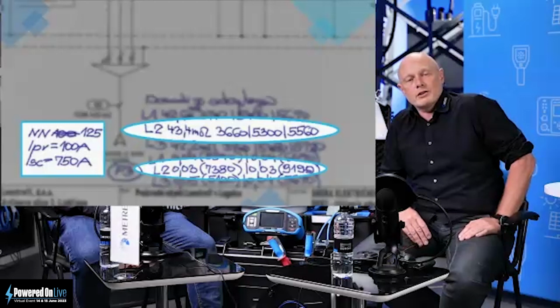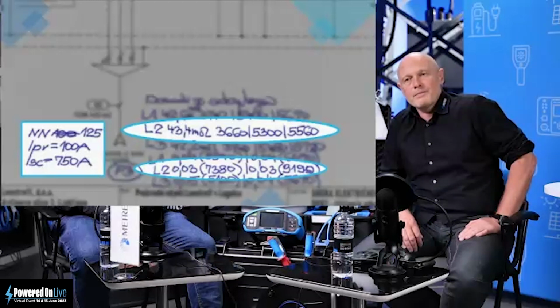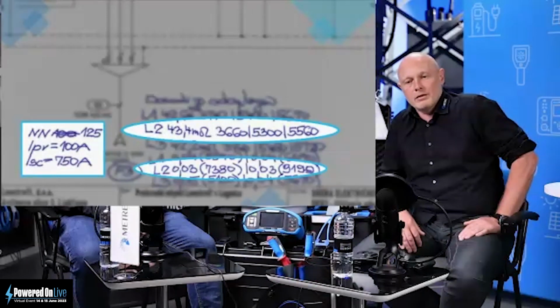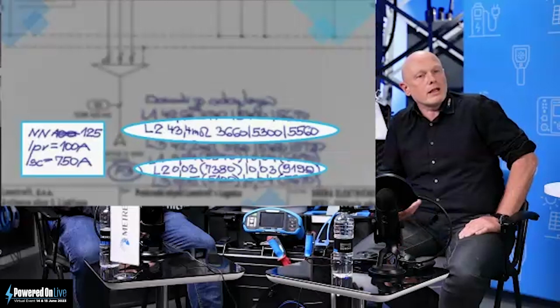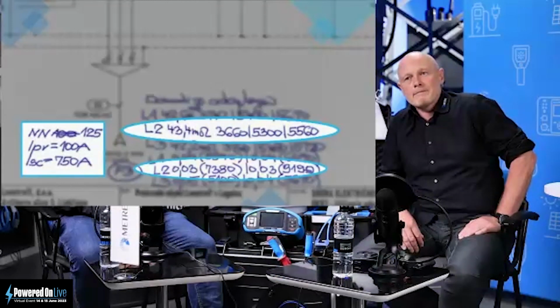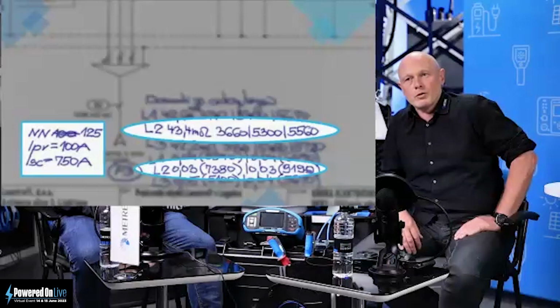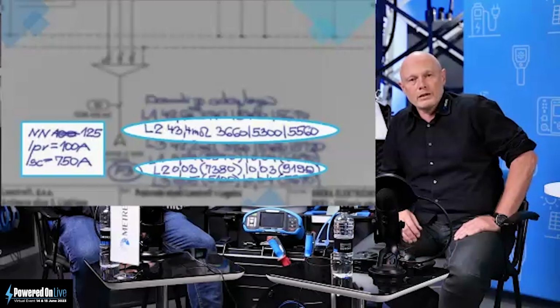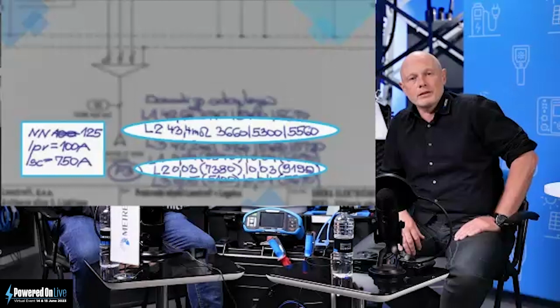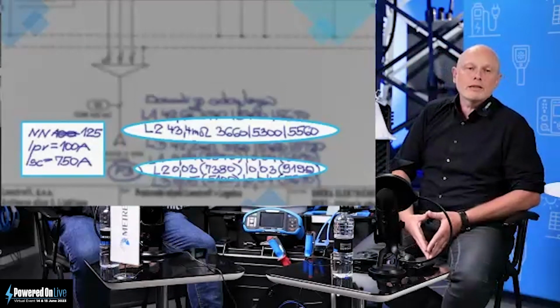We can check this by looking at the results, as shown in the upper circle on the screen. A result of 43.4 milliohms can be easily evaluated. You can also take the measurement two or three times, and when the result is stable, we have properly selected equipment. In the other case, shown at the bottom, a result of 0.03 ohms plus minus 3 digits should be evaluated as completely useless. The measurement equipment is essentially blind in the expected range, meaning it is not properly selected for the test.